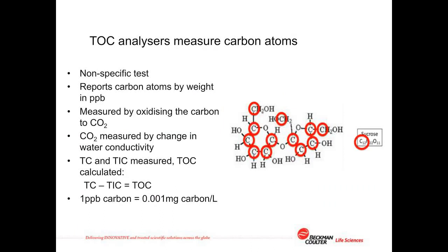Total organic carbon is a non-specific test, i.e. the results of TOC analysis can tell you the levels of organic carbon in the water, but it cannot tell you exactly what those organic substances are. TOC is a measurement of the mass of carbon atoms present in organic material in the water, reporting TOC in units of mass per litre of water, i.e. micrograms per litre, or more frequently expressed as parts per billion.